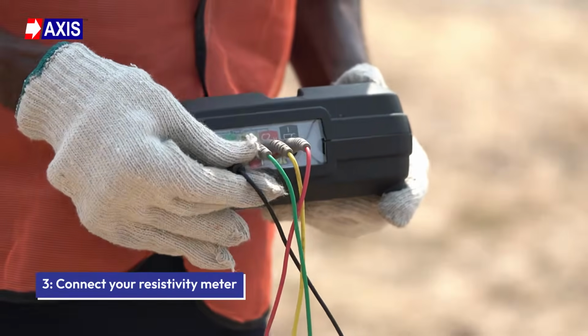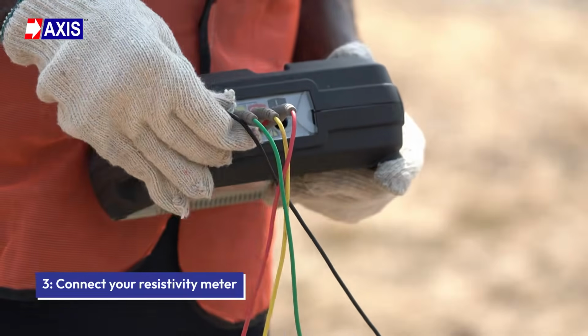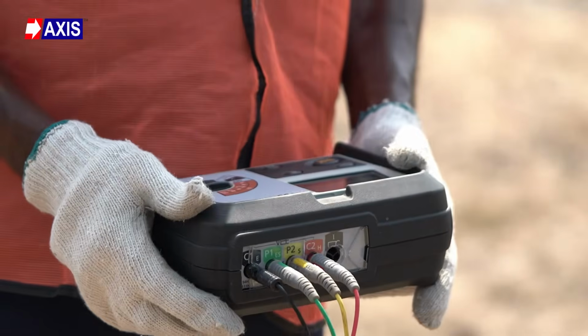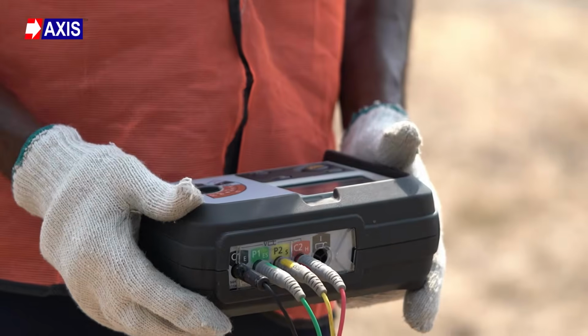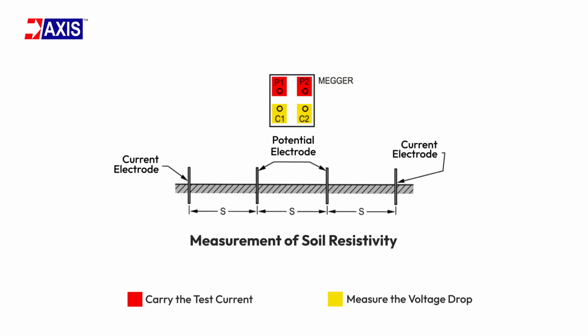Step 3. Connect your resistivity meter. Open the link between terminals P1 and C1 on the instrument. Connect the 4 electrodes to the respective terminals on the meter as shown in figure 87 of IS 3043. C1 and C2 carry the test current. P1 and P2 measure the voltage drop.